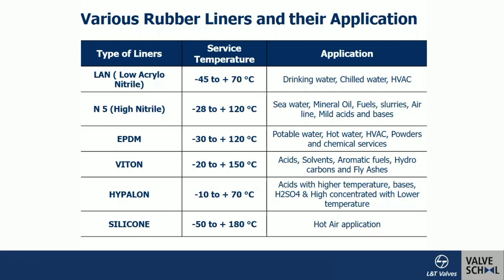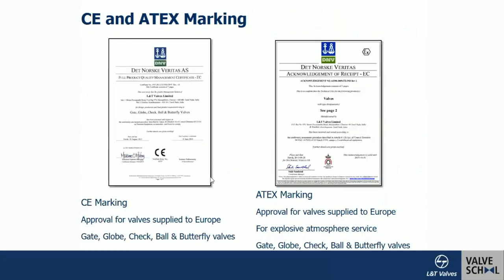Silicone rubber is used for very high temperatures — up to approximately 180°C — for hot-air applications in many process industries. Butterfly valves are also certified with CE marking and ATEX marking in order to work in explosion-prone services and for atmospheric services requiring specific corrosion resistance. CE marking assures quality requirements and enables supply to the European region; ATEX marking is also available, as with other valve types such as gate, globe, check, and butterfly valves.